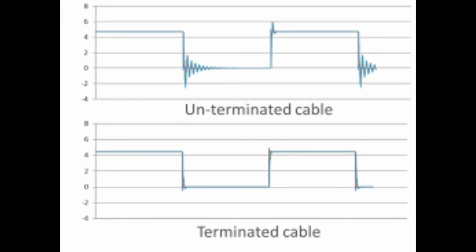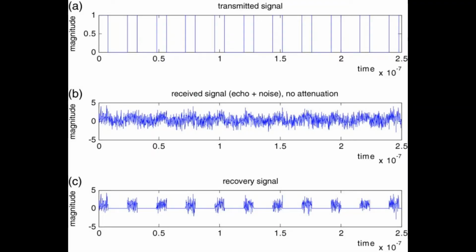For a balanced serial transmission, in case of RS422 and 485, ideally the two ends of the cable must have a terminating resistor connected across its two wires. Without termination resistors, the signal reflections at the alternate end of the cable can cause data corruption. The termination resistance, because of its low impedance, reduces the electrical noise sensitivity. There may be a chance that the receiver is set to echo and so it may be receiving its own messages, as in RS422 and RS485 the receiver is always listening to the transmitted messages.